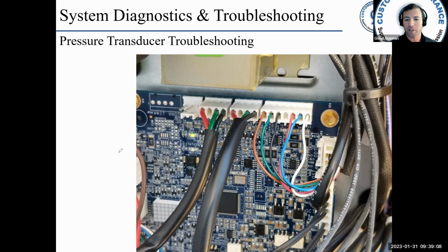I pull P1 and P2 off the board, I swap them, plug it in, and then I look at the user interface. Now, is it a discharge pressure issue or is it still a suction pressure issue? Okay, if it's still a suction pressure issue, then that means the problem stayed with the board. Okay, I switched the transducers and the problem did not follow the transducer, it stayed with the board.